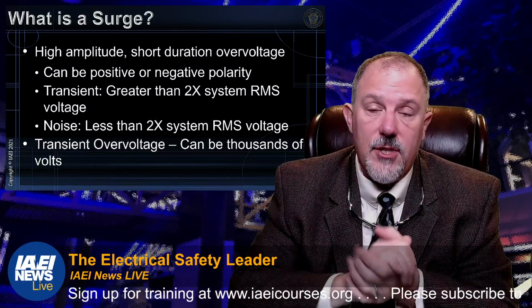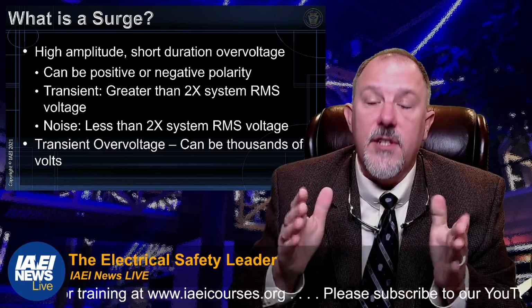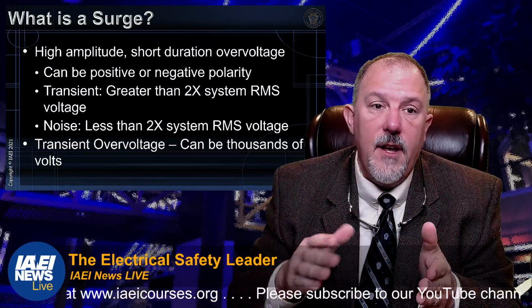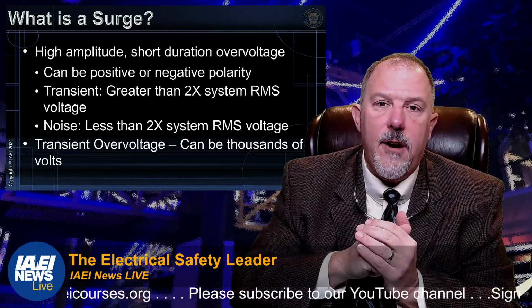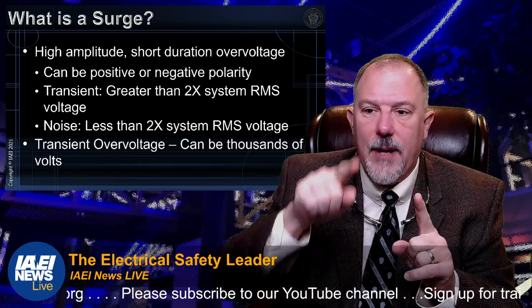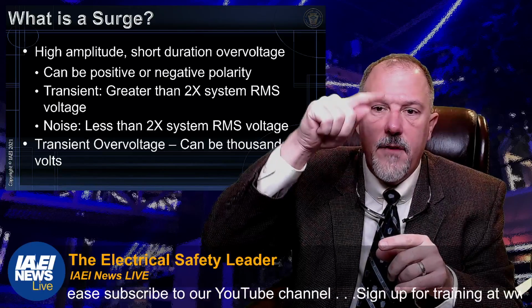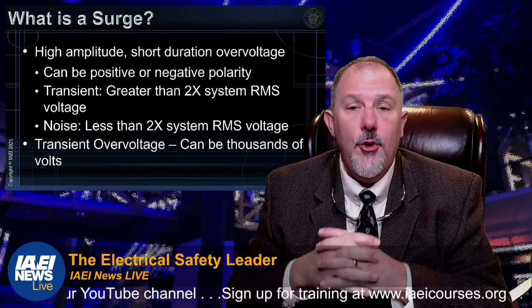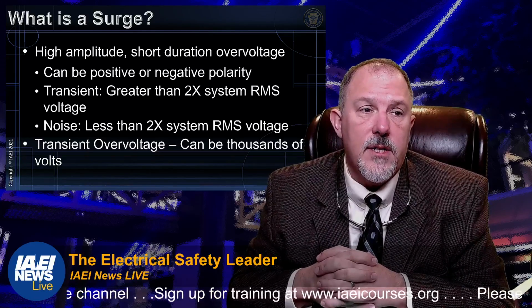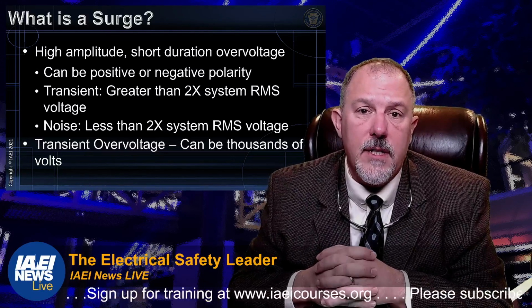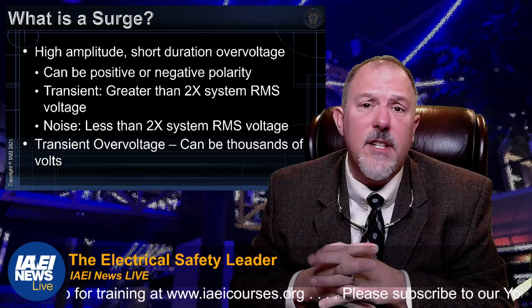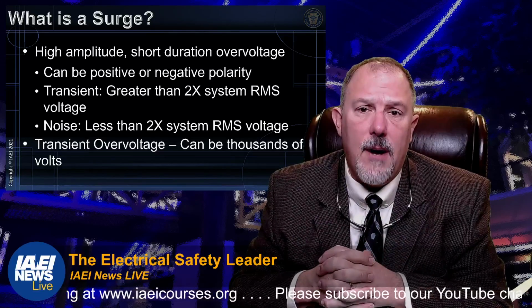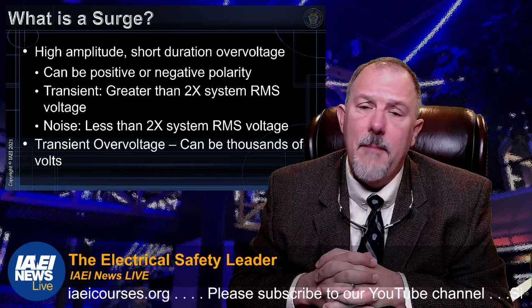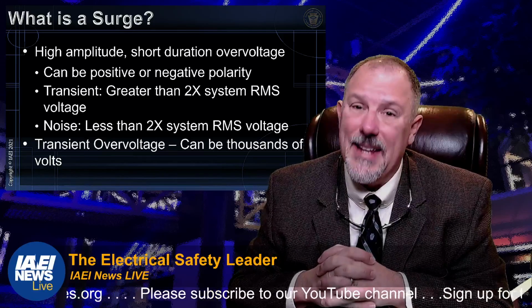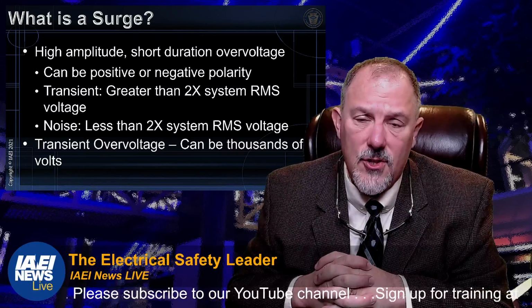Now, noise, if you've ever seen a sine wave that didn't have a nice straight line, it was a lot of little squiggly lines on top. That's what we call noise. Noise is something that rides on top of a system. It could be interferences, various frequencies riding on top of your voltage sine wave. But the magnitude of noise is much less than a transient surge event.